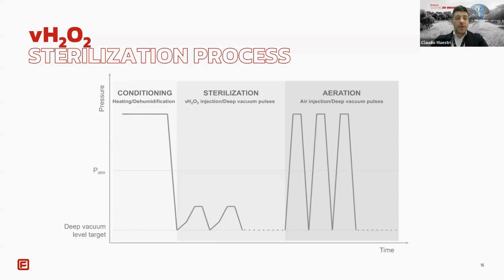And then the third main phase is the H2O2 injection and sterilization. Vaporized hydrogen peroxide is introduced in one or more pulses, maintaining exposure to critical sterilization parameters for a set time. Sensors continuously track temperature and pressure to confirm uniform distribution. And then the post-sterilization aeration. The chamber's ventilation reduces the residual H2O2 in the chamber to safe levels, and a catalyzer is used to split hydrogen peroxide into water vapor and oxygen.